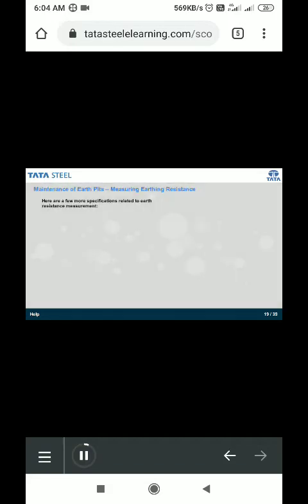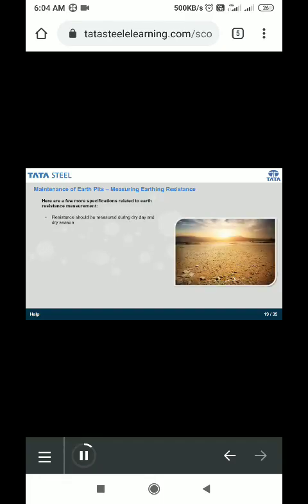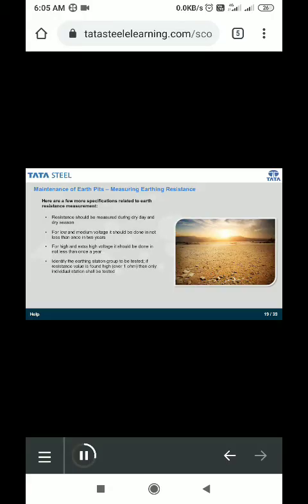So now we know that earth resistance varies from season to season. Well, let us look at a few more specifications in this context. Resistance should be measured on a dry day and in the dry season. For low and medium voltage, it should be done not less than once in 2 years. For high and extra high voltage, it should be done not less than once a year. Identify the earthing station group to be tested. If the resistance value is found high, that is over 1 ohm, then only individual stations shall be tested.